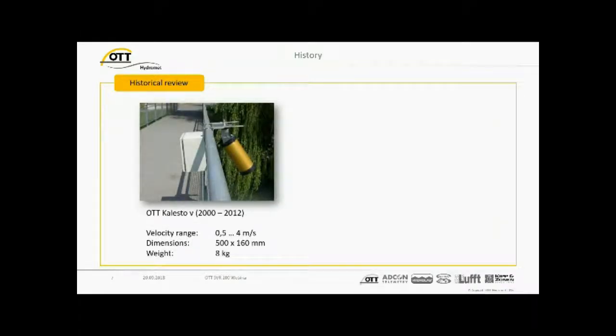From the historical review, maybe one or other of you may remember the old Kalesto V. Kalesto V was a surface velocity radar we provided for a couple of years from 2000 up to 2012. The velocity range was a little bit limited, 0.5 up to 4 meters per second. The dimension was big, as you see in the picture here, a huge tube with a weight of 8 kilograms. This is heavy, and even if you want to install it in the field or you are below a bridge and you need to do this, it was a heavy work.